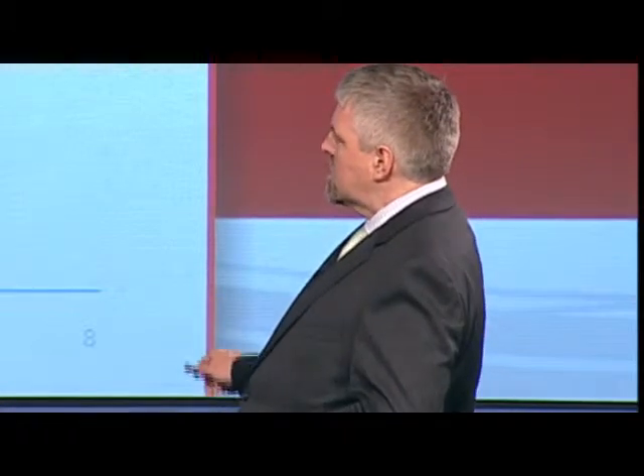These curves here show 0 to 100% CPU utilization against the power consumption of the blade chassis itself. These lines basically lay on top of each other, which I just found absolutely amazing. So anybody thinking that running a data center at 85 Fahrenheit is going to consume vastly more IT load than at 65 Fahrenheit — have a look at that data.